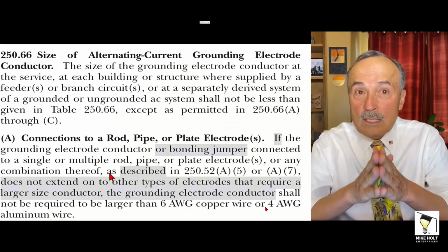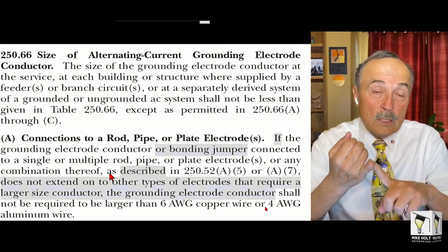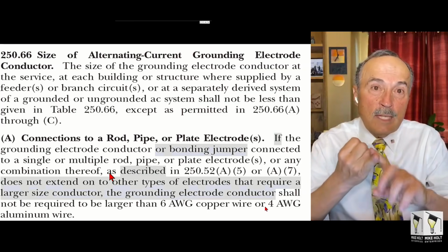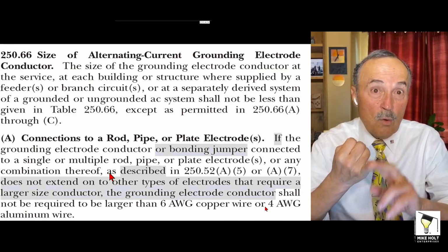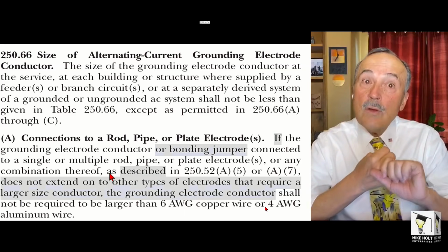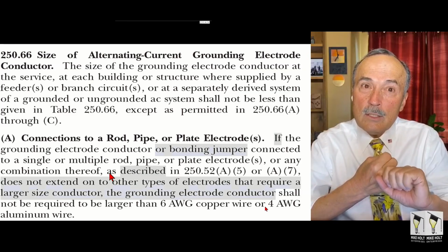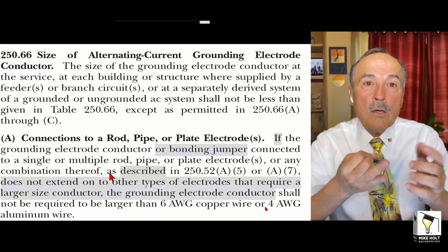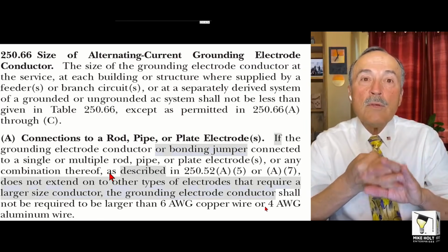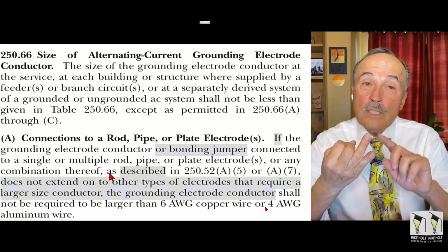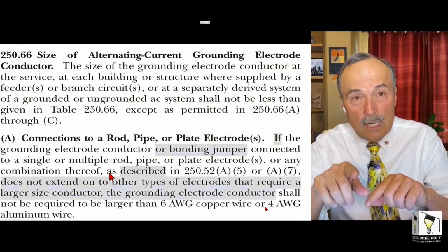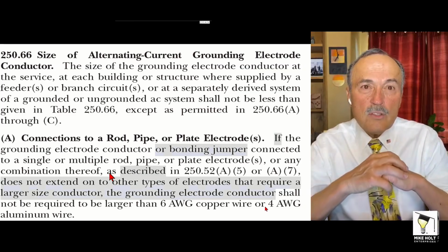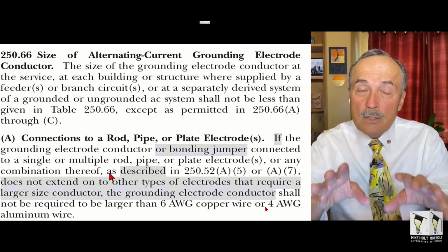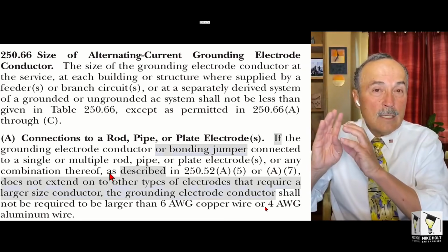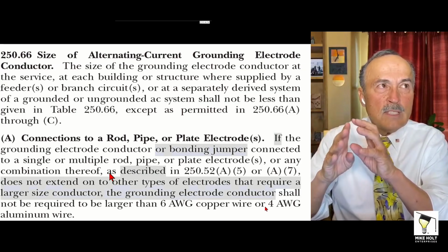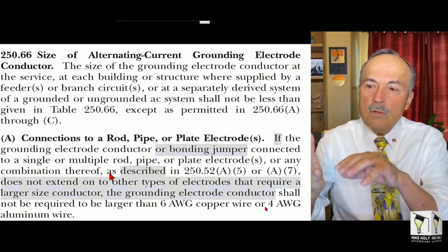250.66 tells us how to size the grounding electrode conductor. Services, remote building, okay, 250.24. At services, you require a grounding electrode conductor. 250.32, 2020 code, requires a grounding electrode conductor at a building supplied by a feeder or branch circuit. Oh, I'm sorry, 250.33 is a remote building. 250.24 is going to be your services, and 250.30 is your separately derived systems, which is primarily going to be your transformers. They all require a grounding electrode conductor to an electrode that is recognized, and I forget what part it is. It's in 250.50 and 52 and 53, okay? And I'm not going to get into those details.